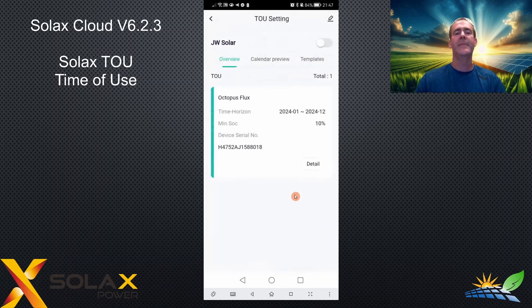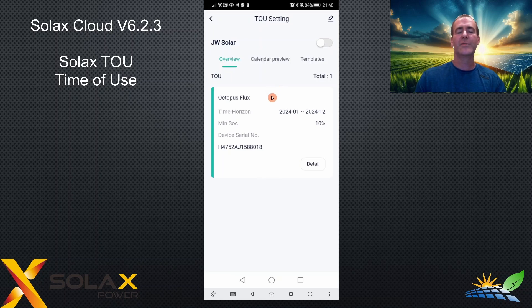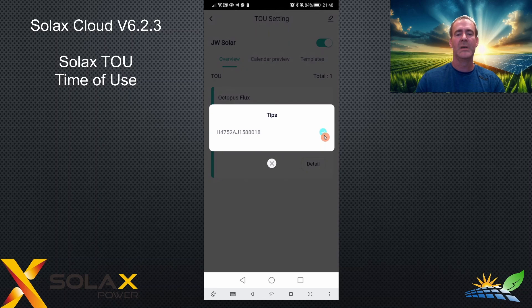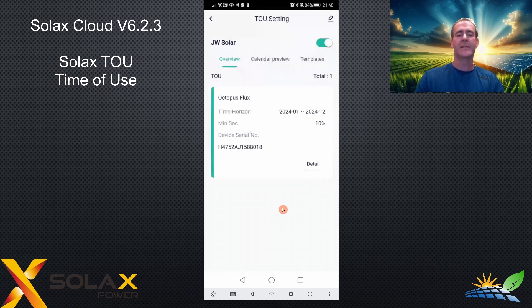Back at the main screen — at the moment it's not sent to the inverter, so the inverter won't follow it. You can set up as many programs as you like. When you want to send a program to the inverter, click the slider toggle at the top. It'll show the inverter, you'll get a buffering indicator, and then a white tick and a turquoise circle — which means it was successful. Click the cross and the TOU is sent to the inverter.